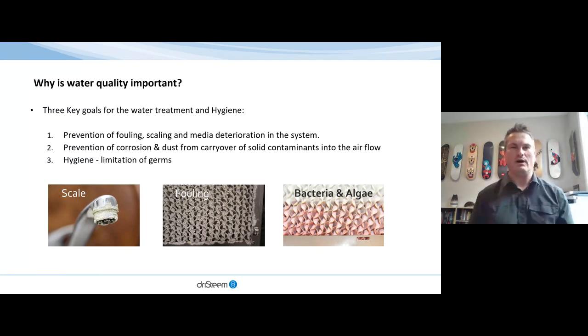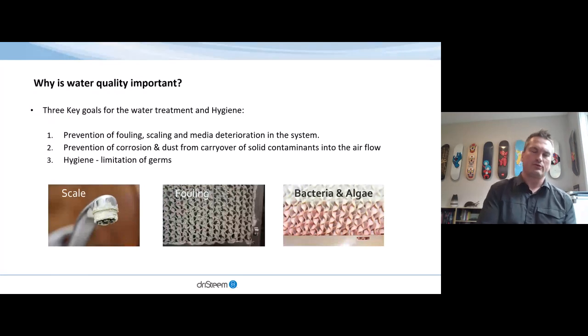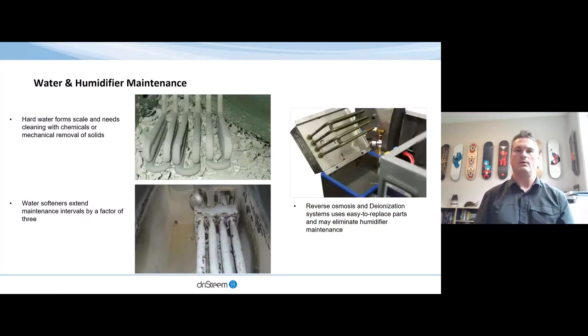Why is the quality of water important when humidifying? Well, the 3 key goals of water treatment in preventing maintenance issues are to prevent or reduce the amount of scale, to prevent fouling, and the hygienic aspect of preventing bacteria and algae growth. So when we look at water and humidifier maintenance, we can see examples here of hard water forming scale and regular maintenance that would need to happen.